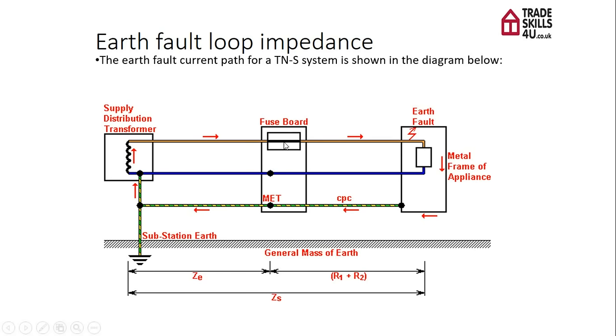When the fault hits the consumer unit or the distribution board, the protective device should operate, so long as the time taken for the current to flow around this loop is within a specified value. We need the resistance or the impedance of this path to be a sufficient value in order for the protective devices to disconnect within the correct time. That's why we've really got to check that the earthing conductor from the distributor or going to our earth electrode is sufficient and does meet those figures.